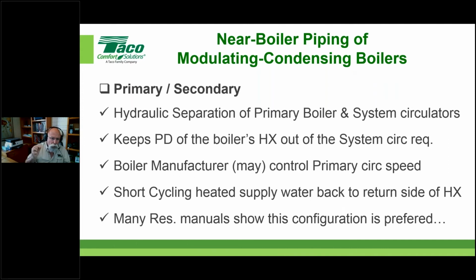One thing I will throw out with this in mind: if the boiler manufacturer allows you to pipe the boiler in series, that means not primary secondary. Some people call it direct flow or variable primary, or there's some other terms out there. If they allow you to do that and your system affords you that opportunity, then by all means do it. Then some of these things that we're talking about in primary secondary don't need to even be considered at that point in time. But there are some caveats to that, so that's why I say just follow the boiler manufacturer's manual, and you'll be safe.